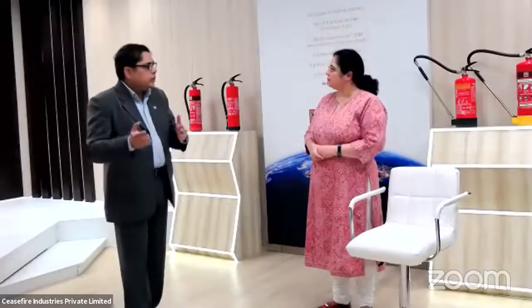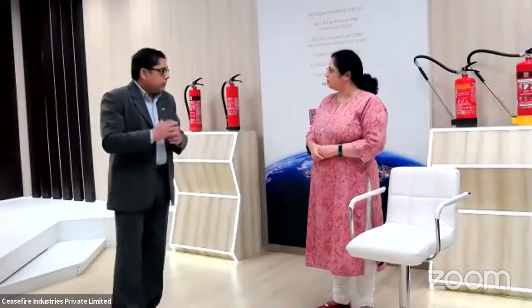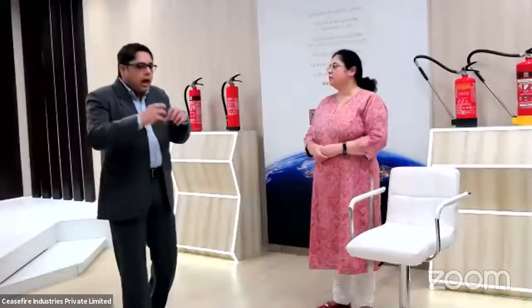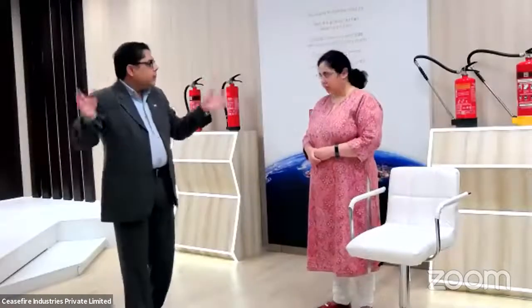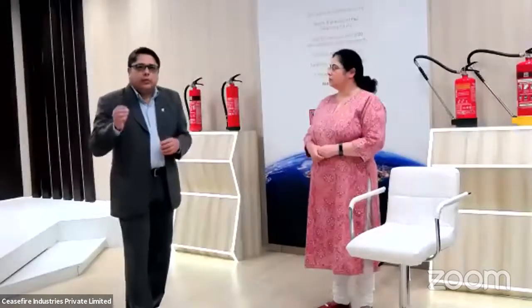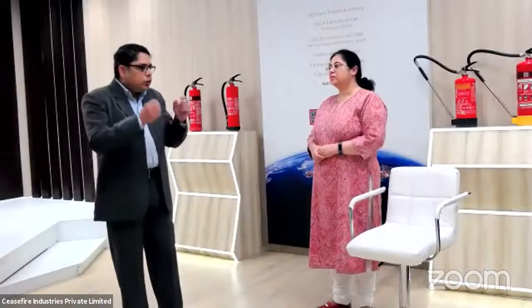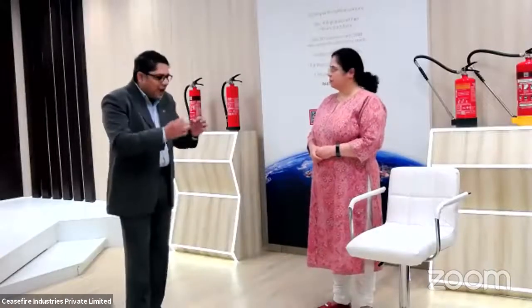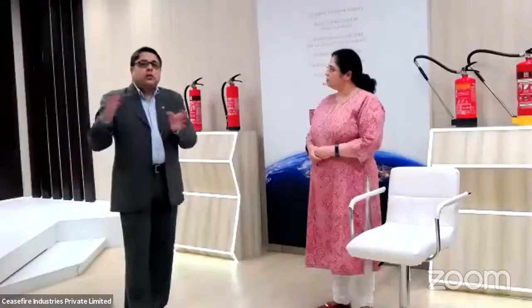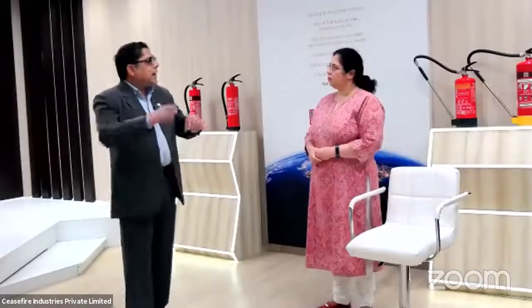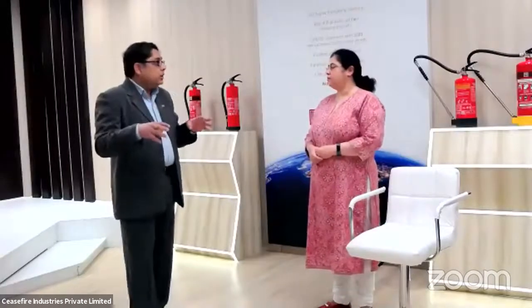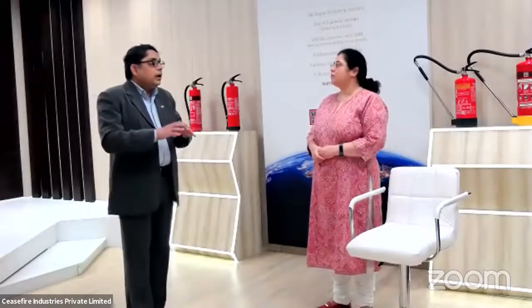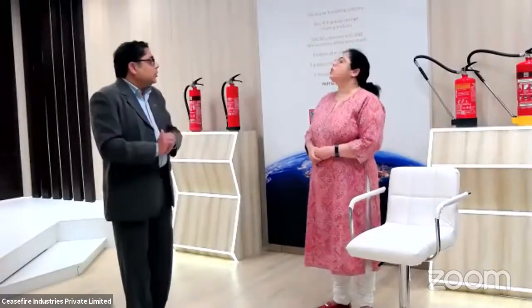On the other hand, we have another tube-based suppression system, which is for more than 2 cubic meters. Here we are using an indirect system, where the requirement is that you might have to expel a large volume of gas in a large area. So we use the indirect system, which is again available in low pressure and high pressure CO2 cylinders. Here the tube only plays the role of detection in the way I've just told you. But the expulsion of the agent comes out through a separate dedicated line with nozzles. So you can expel large quantities in a very short period of time, and you can extinguish fire in larger volumes too. So that is the indirect system.